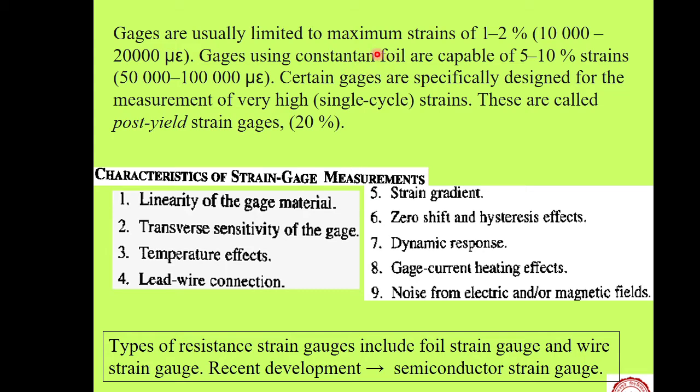So, that is why there are certain limitations in measuring the maximum value of strain. In extreme cases, when we have to use such a stress field, there are special gauges, or we know that we have to use it for a single cycle only. Afterwards, we have to replace it. So, strain gauges in an experiment are usually consumable. You have to use it, and afterwards you have to replace the strain gauge altogether.